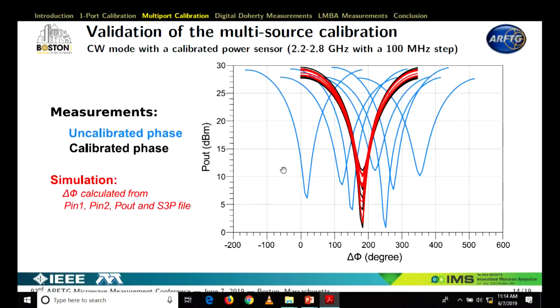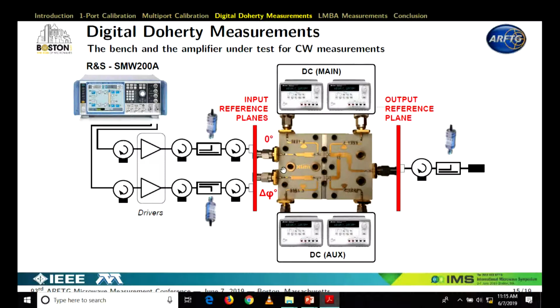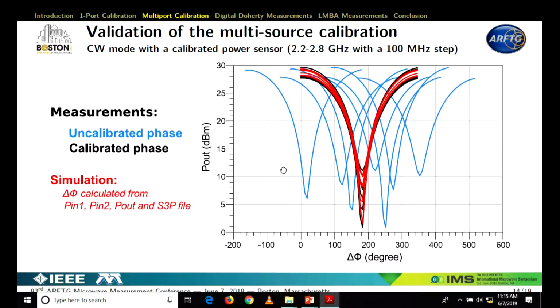And the results are here. Here's an example where we sweep from 2.2 to 2.8 with a 100 megs step. If we do not calibrate in phase, you obtain the blue curves, and it moves a lot. Why? Because at different frequencies, the group delay of the second chain is not the same. If you calibrate the system, as I told you, you obtain the black lines that totally fit the simulation.